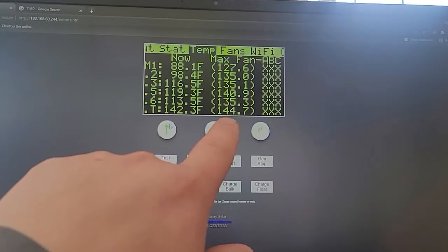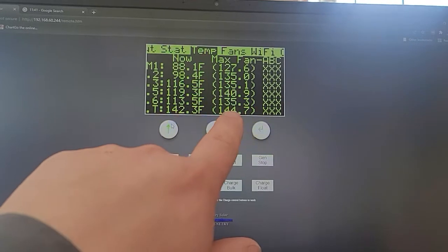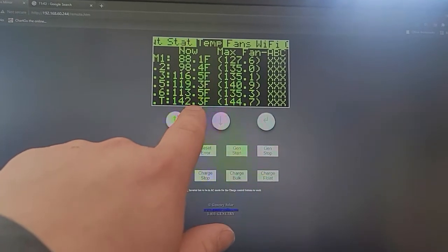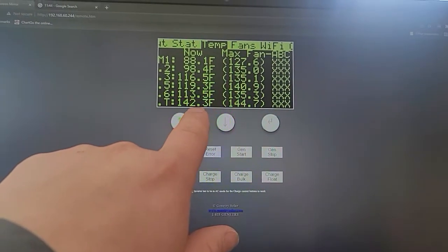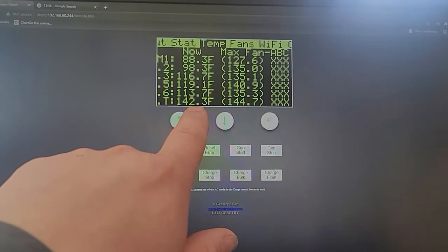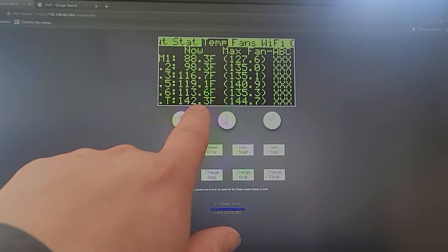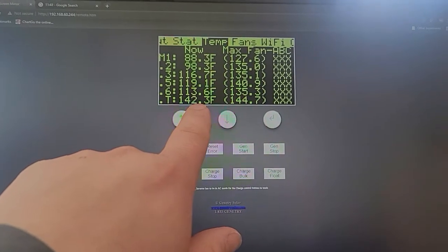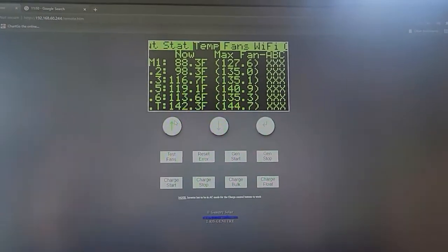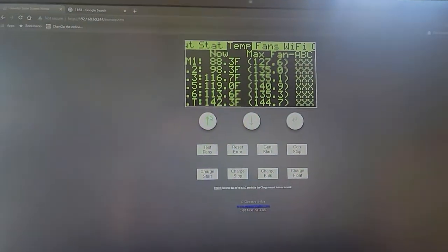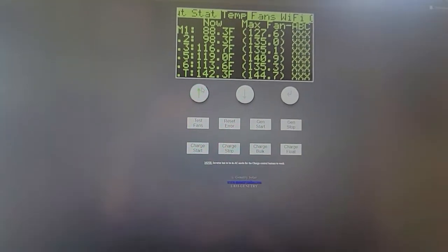So again, as the heat increases, this number should decrease. As this number decreases, the fans will spin down, this number will then increase, fans will spin up. So basically, the cooling system is more than adequate to maintain 12 kilowatts.